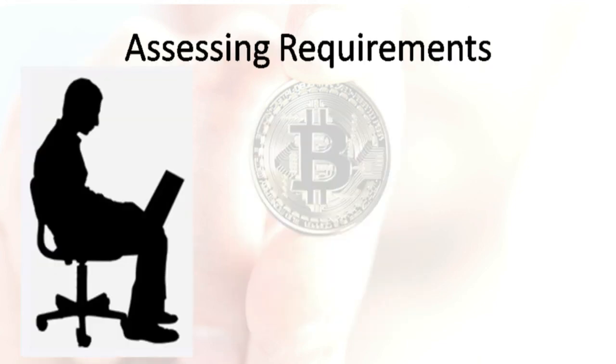There are only a handful of requirements of the facility design that will affect your long-term cost, availability of system, and overall success, more so than how you define your power requirements. For example, you will run out of power before you have filled your space with mining rigs if you underspecify the amount of power you need. On the other hand, if you overspecify your energy requirements, you will pay more for your space than you need.